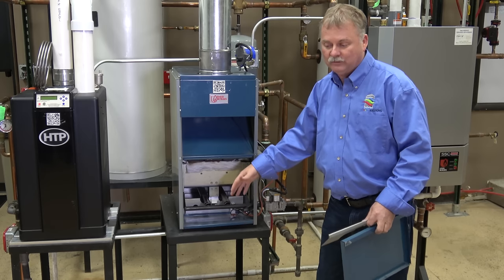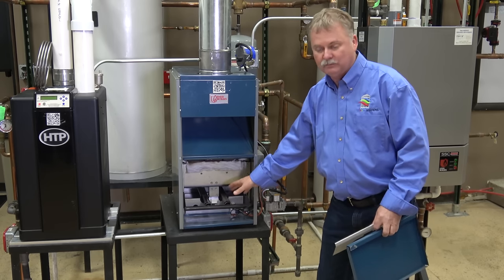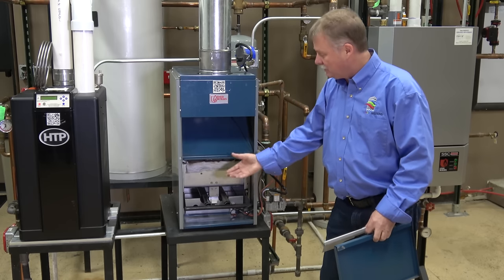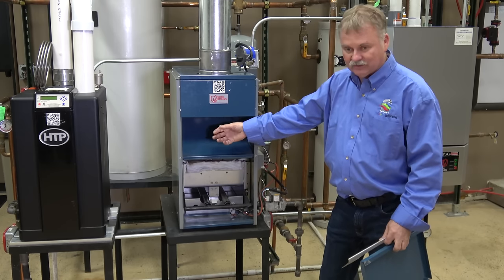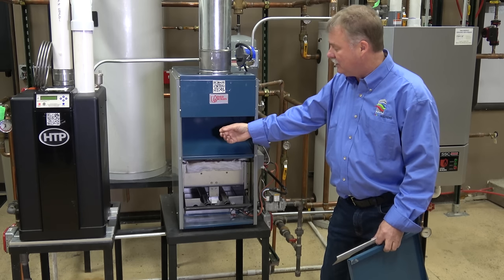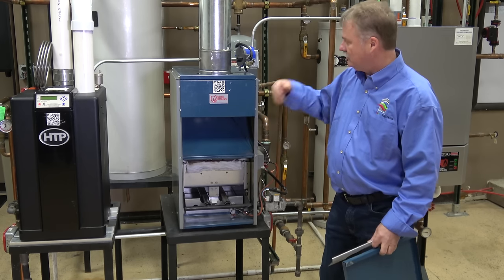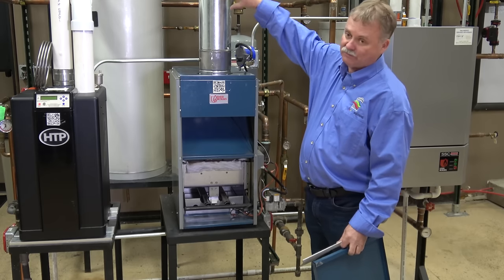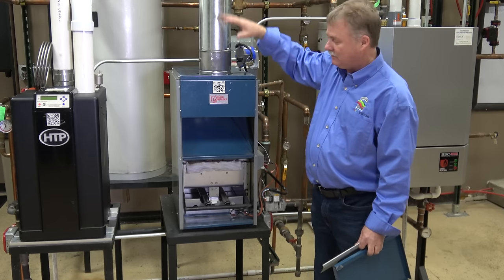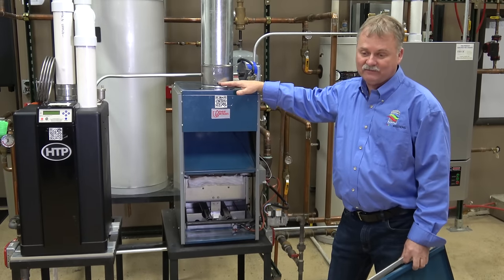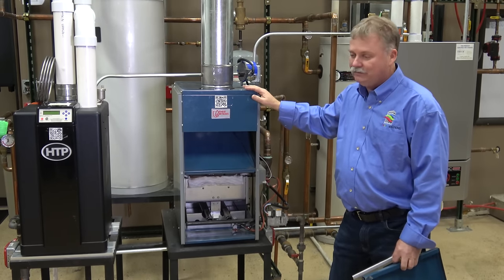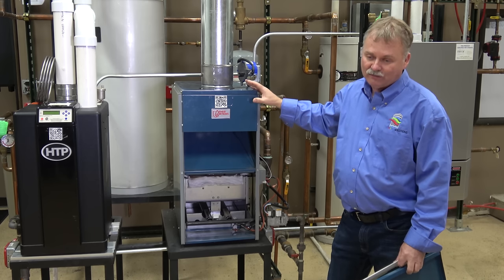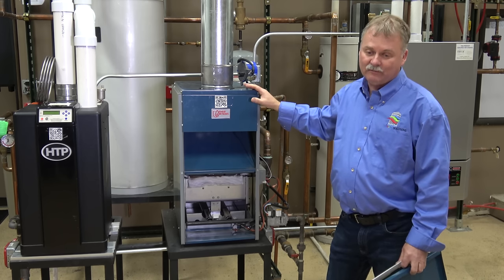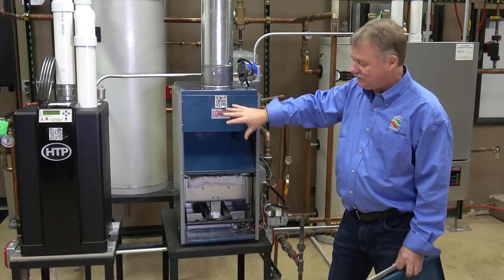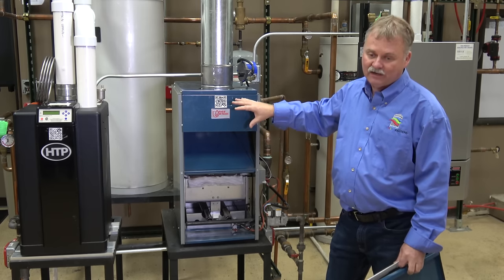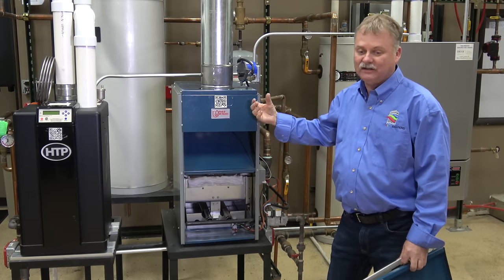So in the boiler room, there are vents in the doors or whatever to allow air for this boiler to create the combustion, to go between those sections to transfer that heat out of the flame and the fire into the water, which circulates through the system, and all our exhaust gas goes up and out the flue and out your chimney. These boilers range from about 80 to 85% efficient. There are a few new safety controls and outdoor reset controls on these boilers that have been required by the government for the last couple of years. But the basis of this boiler is still a good, standard, high-quality cast iron section that does all the heat transfer.